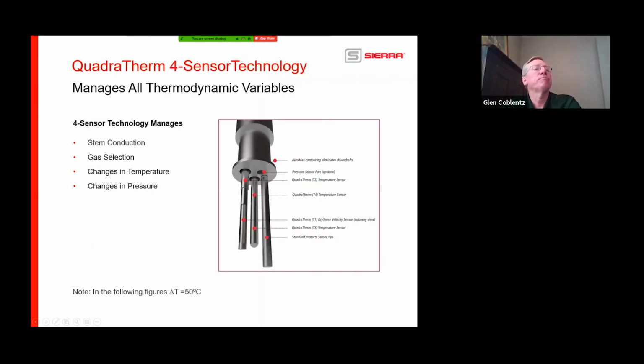Again, just as a review here, the QuadraTherm brain combined with the sensors, we're keeping track of everything. The stem conduction, that's the heat going up the stem. What gas is it measuring? Are the temperatures changing? Are the pressures changing? Now, thermal mass flow is a direct mass flow measurement. So the only thing that's happening with changes in temperatures and pressures is the molecules are moving closer together or further apart. So that's affecting that heat transfer. But we keep track of this anyway, because if you get to various different extremes, we need to know that and need to make adjustments in that calculation.